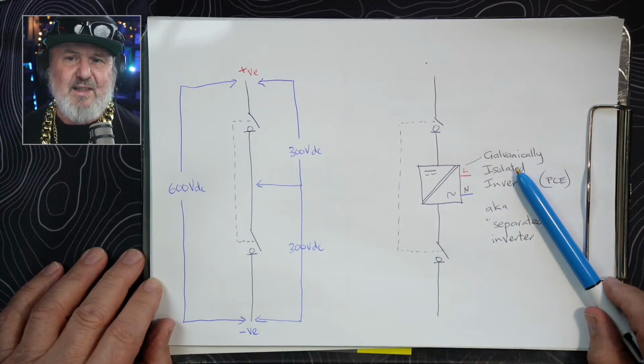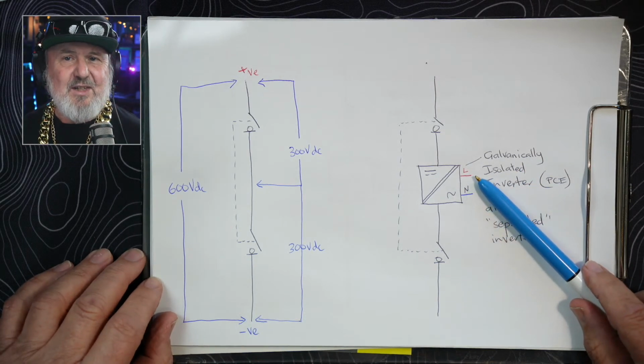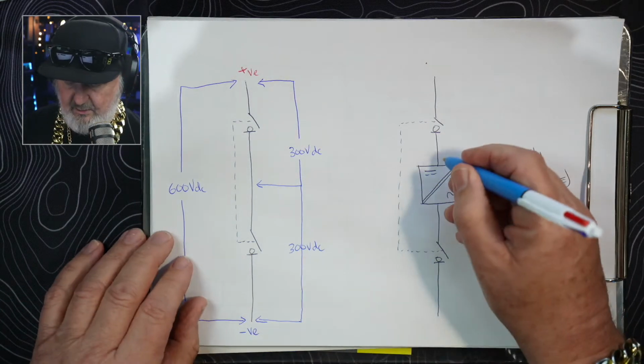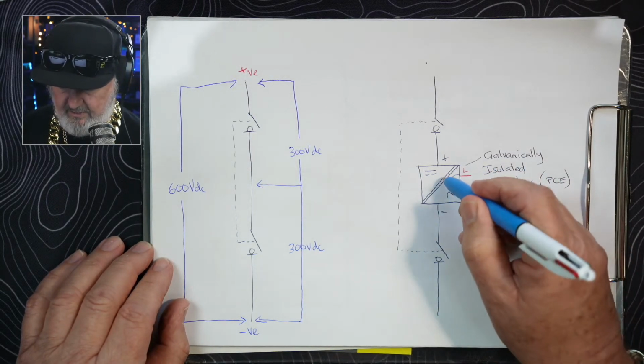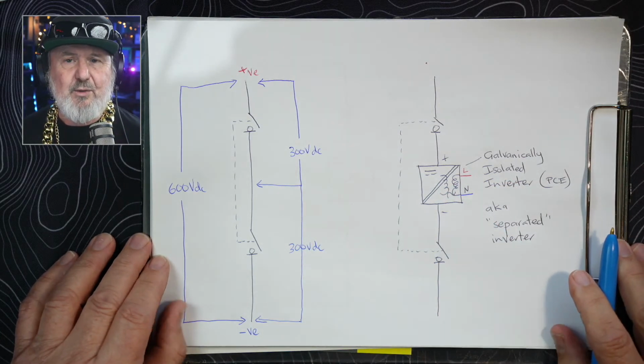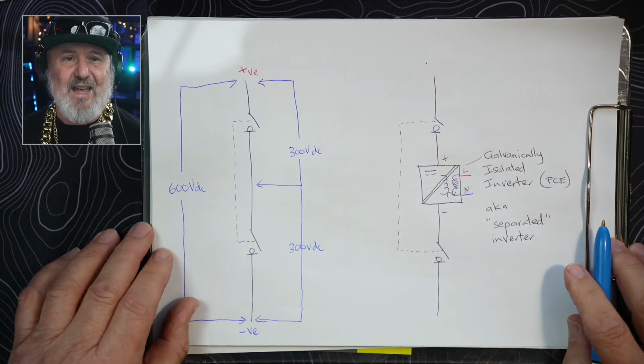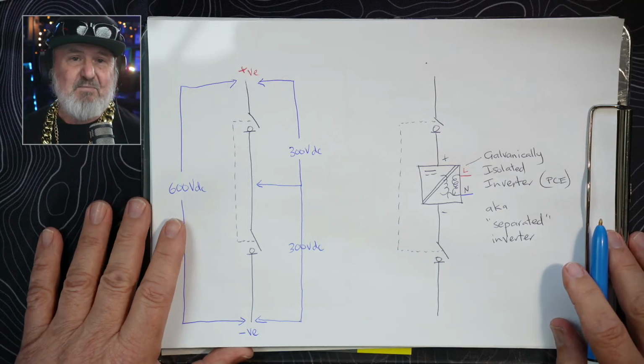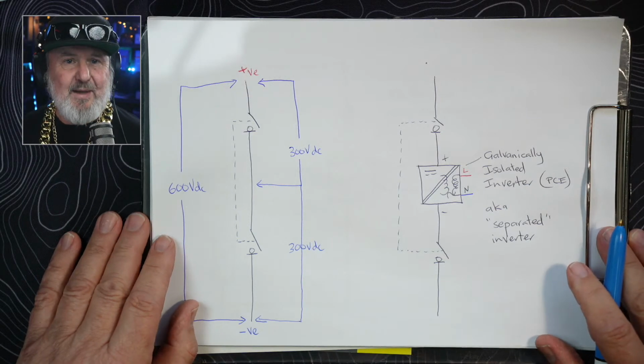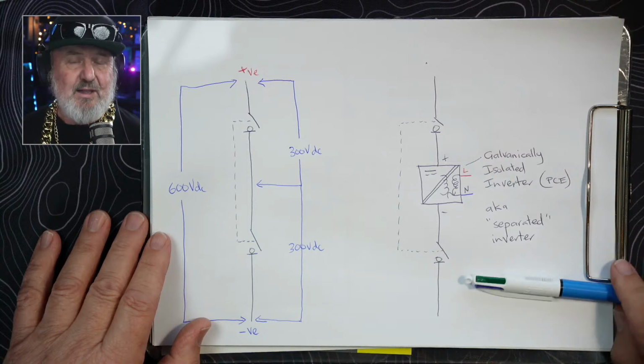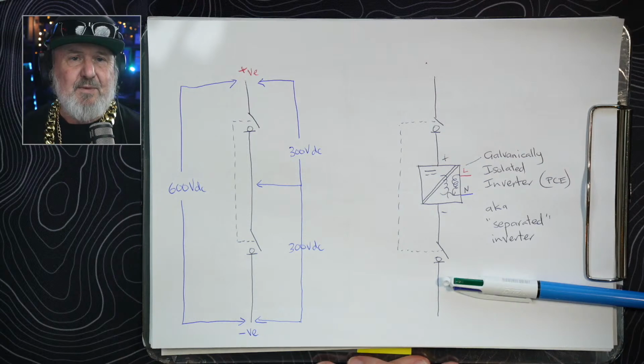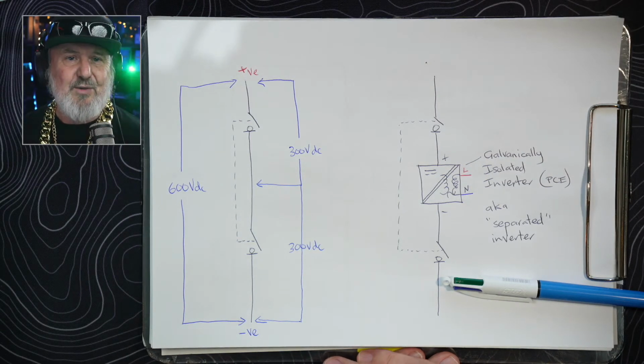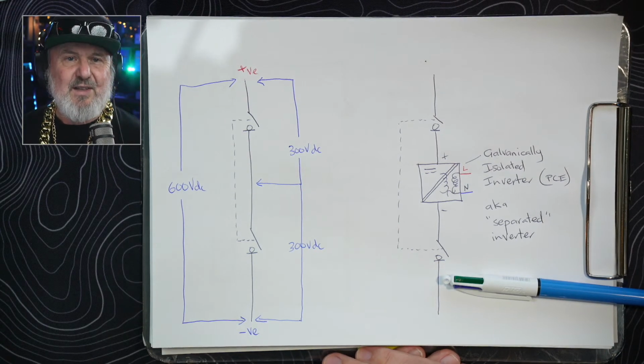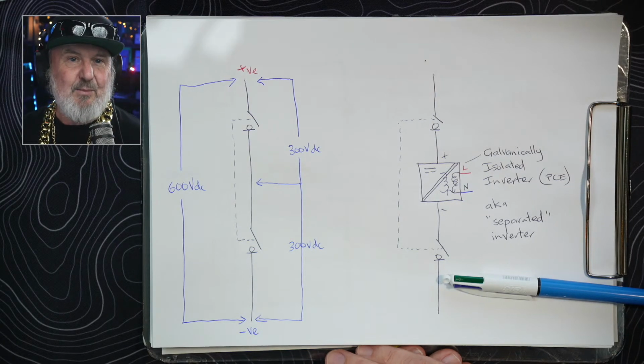What I've shown here is a galvanically isolated inverter. Now, galvanically isolated means that between the AC side here, active and neutral, and the DC side here, so we've got positive and negative, there's effectively isolation, and that's done by a transformer. So we have inside an isolating transformer, so no electrons from the DC side are capable of leaking to the AC side. Galvanically isolated inverters were the norm up until about 10 to 15 years ago when they all went away. Now, there's nothing illegal about galvanically isolated inverters. In fact, for off-grid applications, they're really very common, and particularly if you've got a battery system that is extra low voltage, you do need galvanic isolation between your battery and your AC or any other source that's LV that feeds that PCE. But let's talk about grid connect systems here. So this galvanic isolation does give some definite safety advantages, but the industry moved away and moved to transformerless.